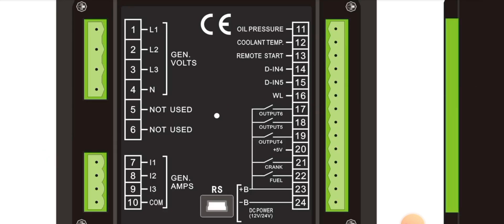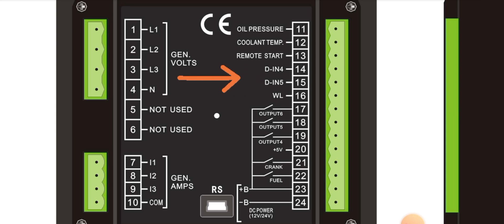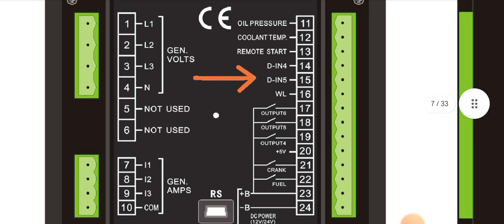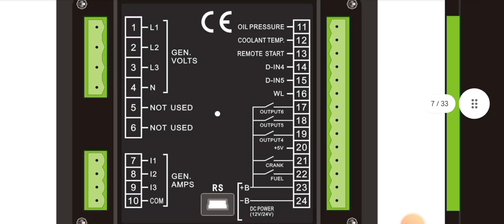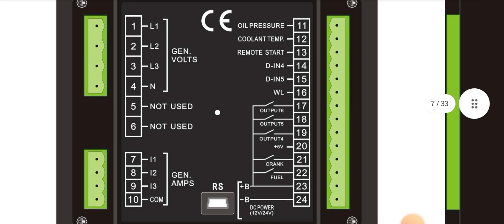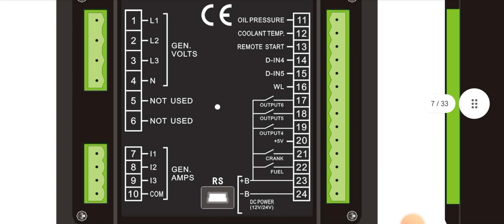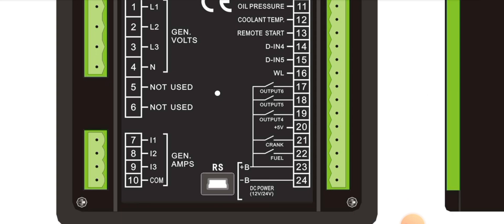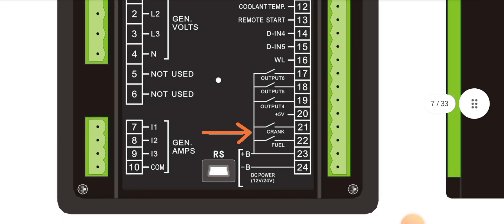Pin 11 is the oil pressure input, pin 12 is the coolant temperature input, and pin 13 is the remote start signal. Pin 14 is a digital input and pin 15 is DIN5. We will explain these pins further in future videos.